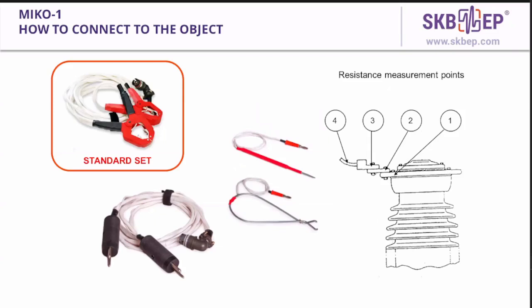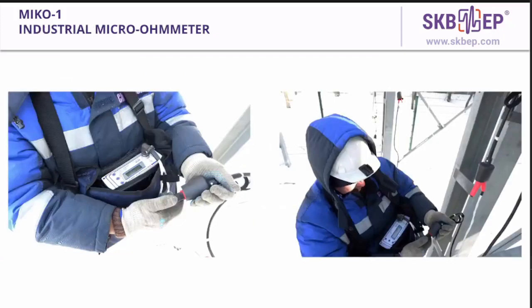On this slide, in the left top corner, in the red line, you can see the test cables that come in the standard complete set. All the rest can be ordered from the additional accessory set. This is an example of usage. You can see the guy holding the instrument. And these measurements were performed at an SF6 live tank circuit breaker at one of the universities where our company performs trainings.